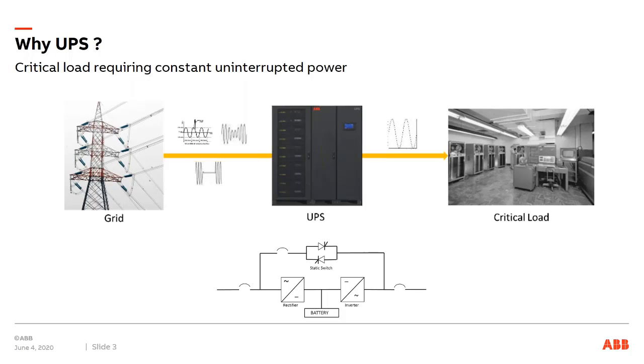Whatever noise may come in may be able to make it through the static switch to the critical load and cause problems. In economy mode, the inverter will be able to kick in automatically and start to feed power in less than a quarter cycle. So that part of the operation is not critical. It's more the notion, that little nagging doubt in the back of the facility manager's mind, that something has to happen. If power fails when they are in economy mode, the inverter has to kick in. And the fact that there's unfiltered power.